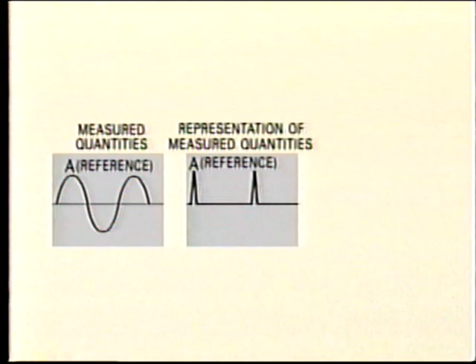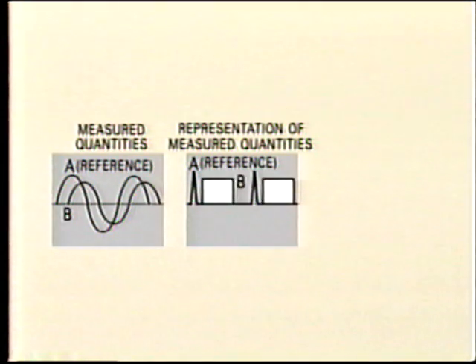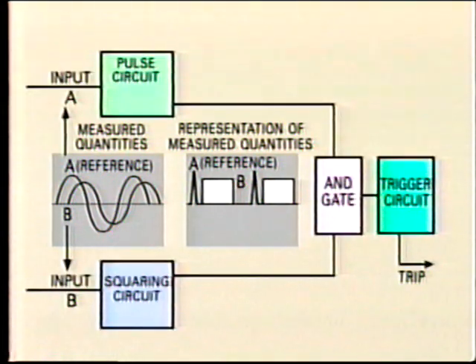Many overcurrent and other relays require directional elements. This is generally achieved by phase comparison. Now, we saw an example of this in the last segment, applying the coincident detector. Another coincident method uses a pulse to represent the peak value of one measured quantity, say the polarizing or reference voltage A, while the second quantity, B, say current, is represented by a square wave. Here is the logic diagram.